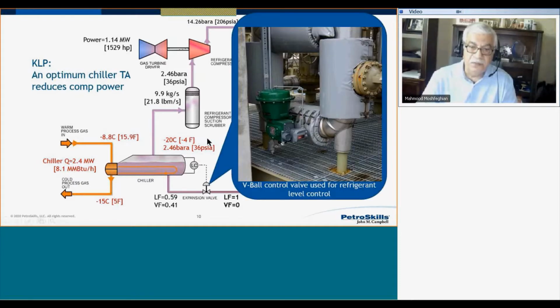So one of the important pieces of equipment is this LCV, level control valve or expansion valve. Normally it's a V-Ball control valve used for refrigerant level control, but at the inlet the pressure is high, which is dictated by the condensing temperature. For our case, about 200 psi, and the liquid fraction is 1, vapor fraction is 0.